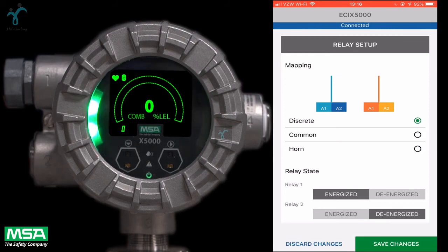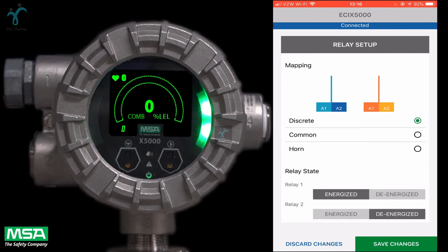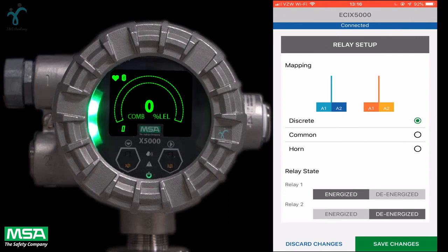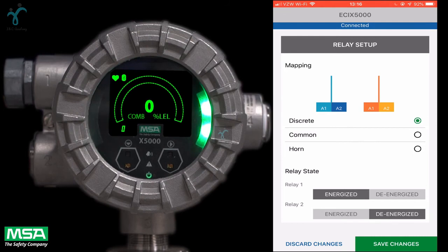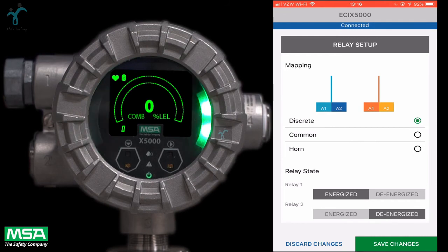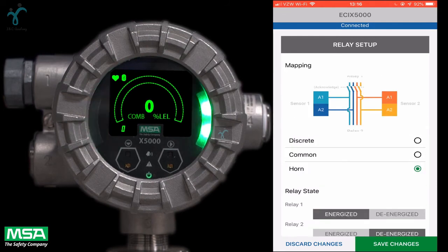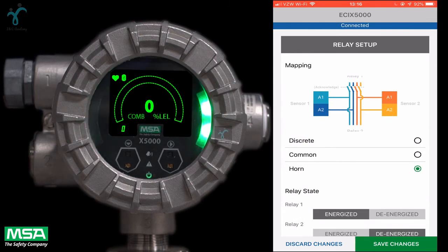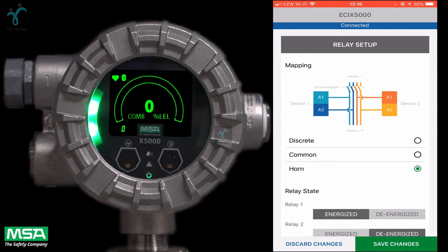Discrete allows for separate actions for each sensor. Relay 1 is actuated by sensor 1 alarms and relay 2 is actuated by sensor 2 alarms. Horn mode is designated to allow local acknowledgement of a relay-triggered horn.